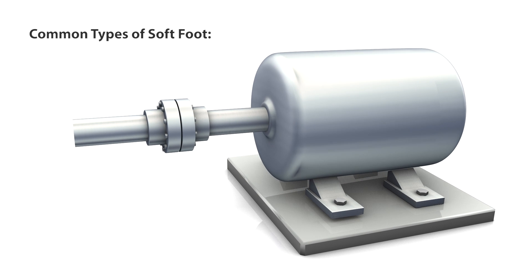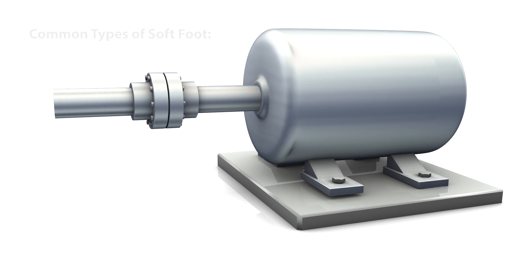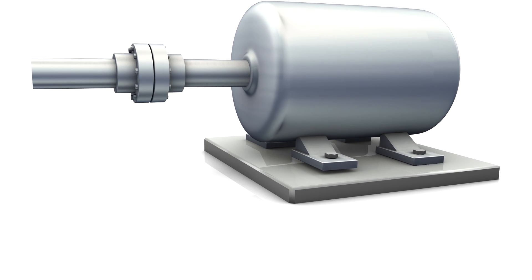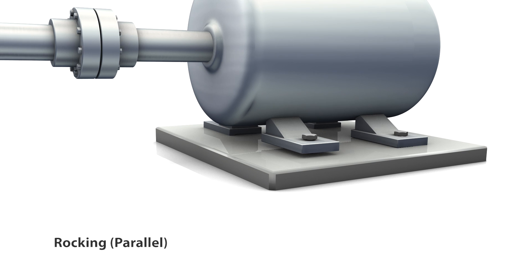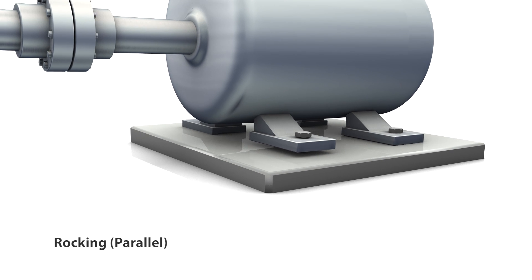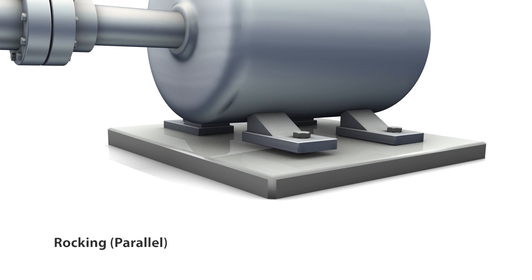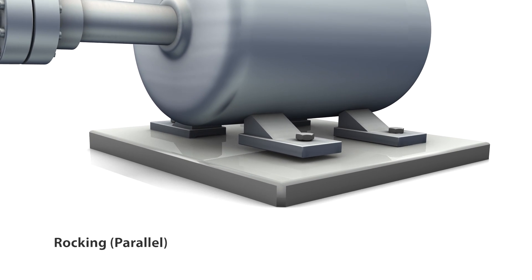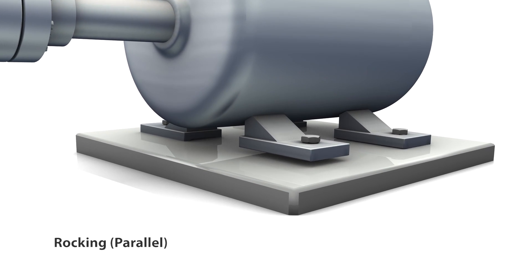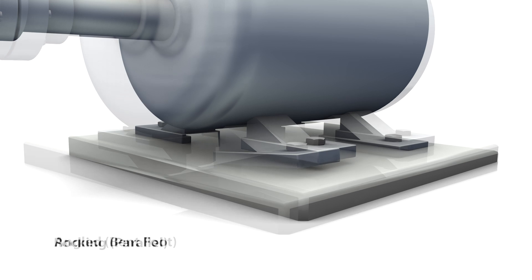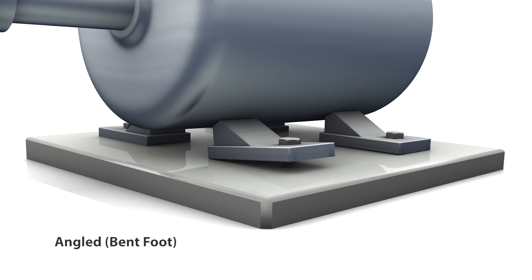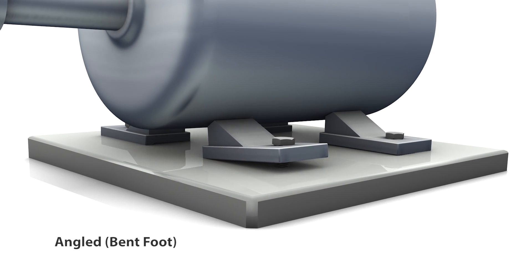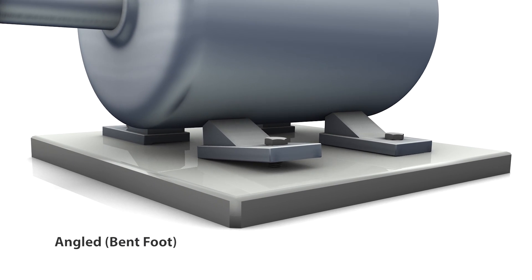Common types of soft foot conditions include soft foot rocking - the situation when a foot that is parallel to the machine frame seems shorter than the others, and angled soft foot occurring when a machine foot is bent at an angle relative to the machine frame.